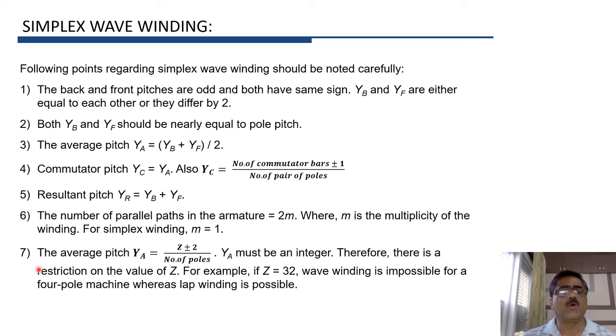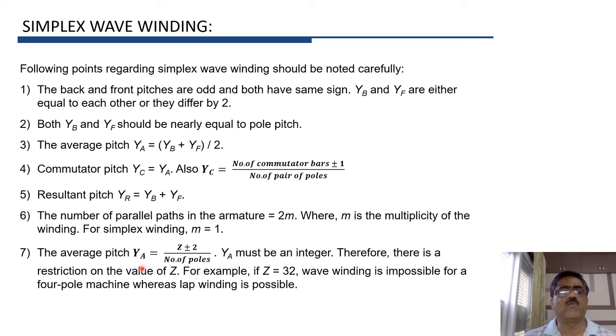One more important point: in case of simplex wave winding, the average pitch YA = (Z ± 2) / P, and YA must be an integer — only then is the winding possible. For example, if Z = 32 and poles = 4, then YA = (32 ± 2) / 4, which is not an integer. Therefore, wave winding is impossible with 32 conductors and 4 poles.